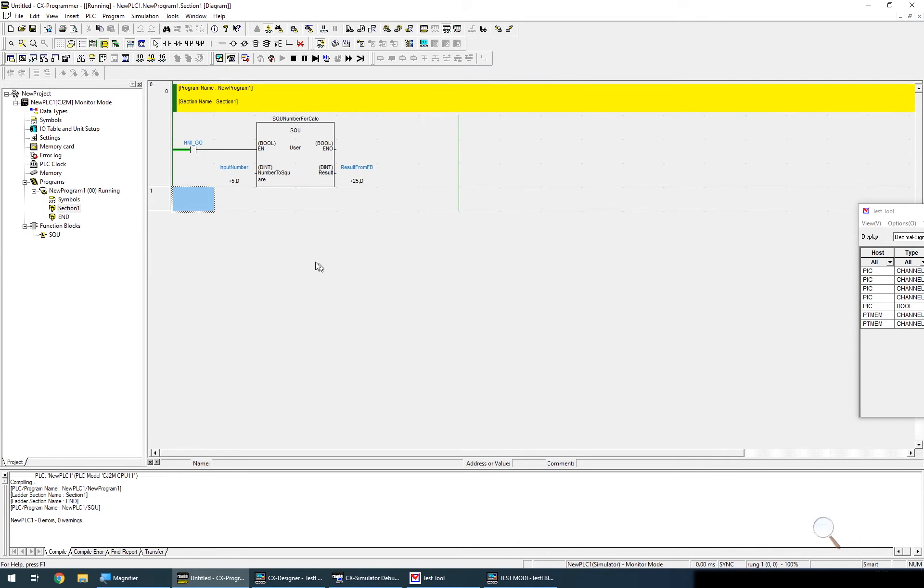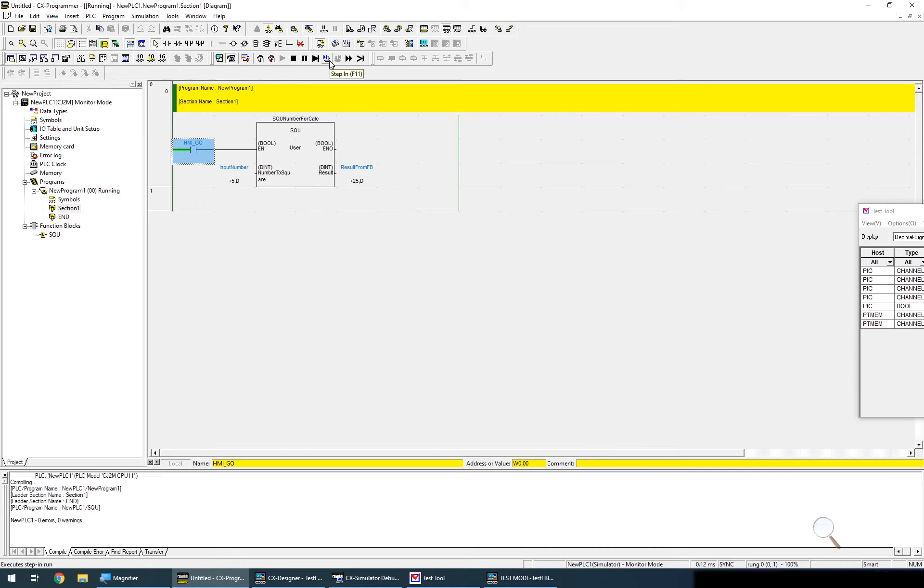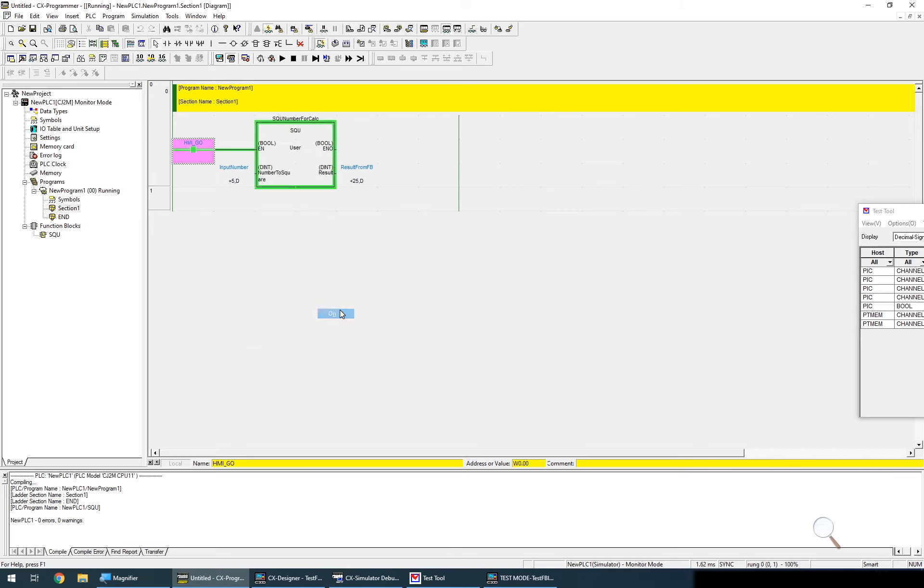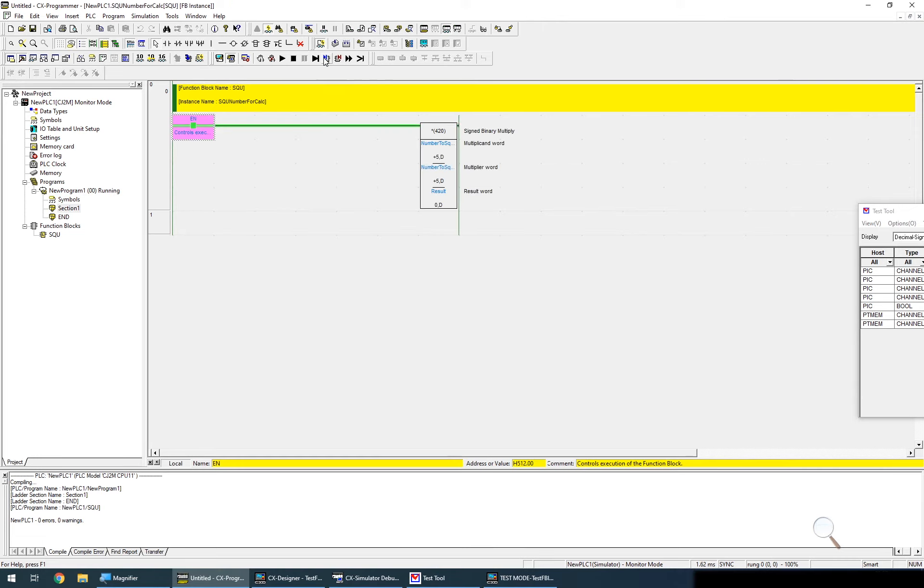So we can actually debug our function block by simply selecting our input here and selecting from the debug menu F11. I'm going to right click and I'm going to set that on, and then I'm going to use the F11 button to step through. So now it's selected my function block and now it goes into my particular code that's part of that function block and you can see here that it says multiply this number which is set to five by five and the result is zero.